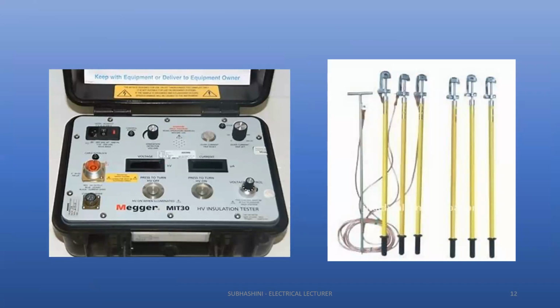So this is the Megger which is used for HV systems. As I have already said, we have 500 volt types of Meggers. One is the hand driven crankshaft movement Megger, and one is battery operated. But for an HV system, we cannot go for hand driven Meggers. We cannot drive it, that may be too heavy, and a generator used to produce a very high voltage, suppose 2000 volt or 3000. HV means we require high voltage, so in those conditions we cannot use a generator to produce the high voltage. So we have to go for battery operated.